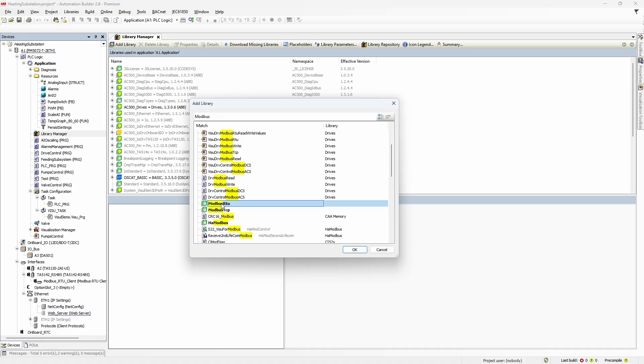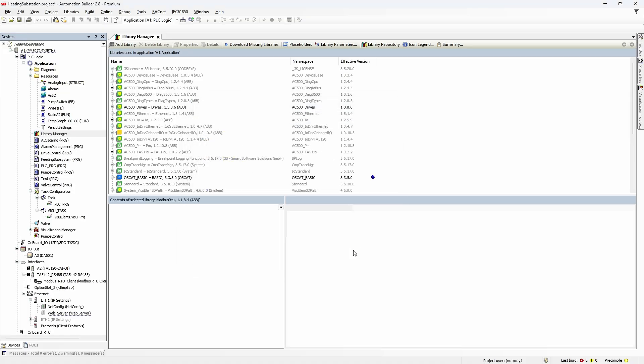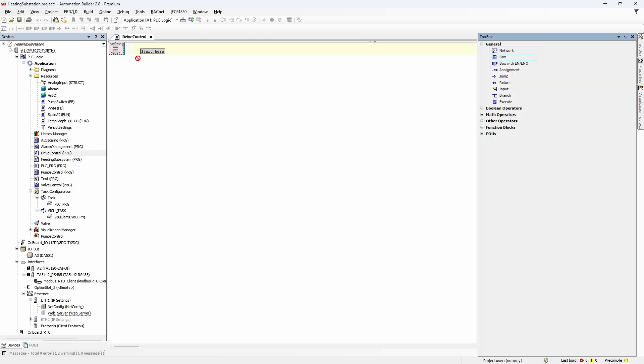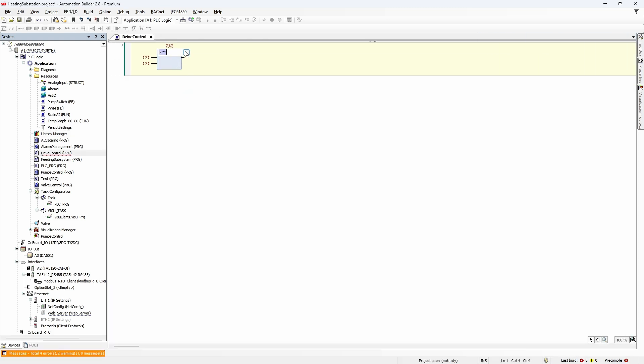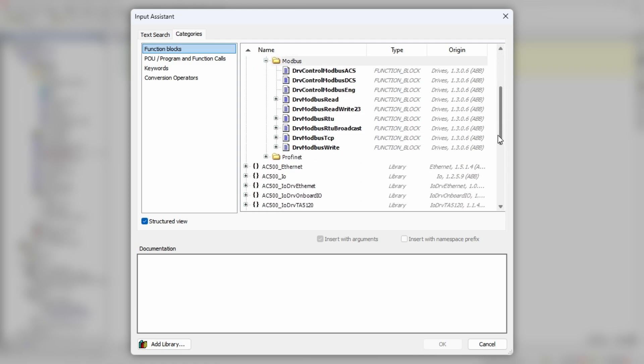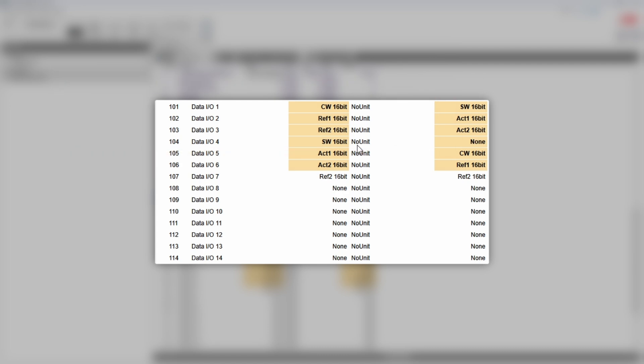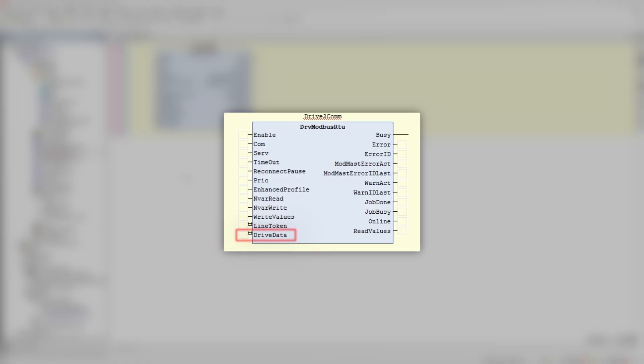Unlike with PROFINET IO, with Modbus RTU you need to program the communication exchange. For that you would need the drives and modbus rtu libraries. In the drive control section, add a box and find the drive modbus rtu function block in the drives library. Basically, what this function block does is write control word, reference1, and reference2 to the drive, then read status word, actual1, and actual2 from the drive, and pack it into one data structure called drive data.